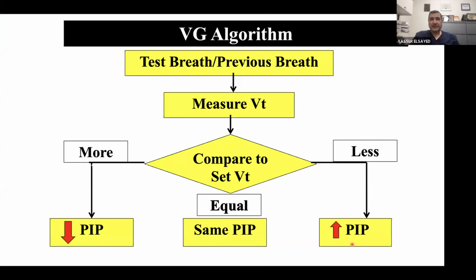Again, this graph will explain the same concept. So we have the measured tidal volume. On the machine, you have 2 numbers for the volume. You have your preset tidal volume, which is a fixed number, 5, 6, or whatever number. And then you have the measured tidal volume. The machine measures it from the expiratory limb, and that can be variable. So based on the measured tidal volume compared to the set tidal volume, if it is less, the machine will apply more pressure. If it is more, the machine will apply less pressure to get the measured almost equal to the preset tidal volume.